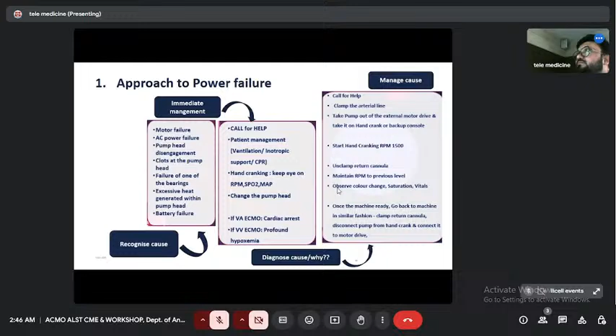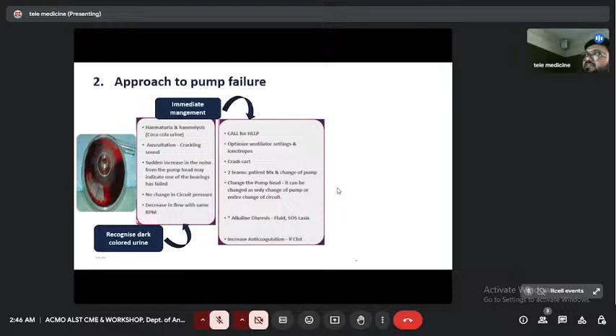This is pump failure. How to recognize it? The patient will have hematuria, hemolysis, Coca-Cola urine. On auscultation of the pump head, you will hear crackling sounds and a sudden increase in noise, with no change in the circuit pressures. Then that means there is a pump failure. How to manage that? You have to again call for help, increase the ventilator settings, and keep crash cart ready. Two teams: one for the patient, one for the ECMO machine management.